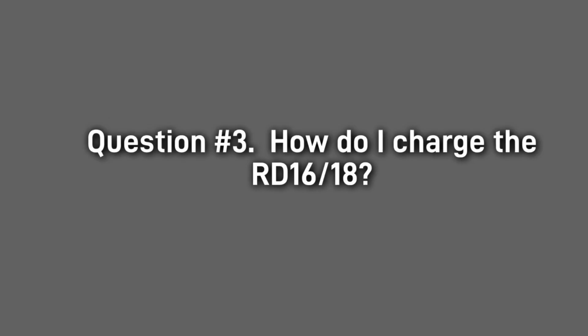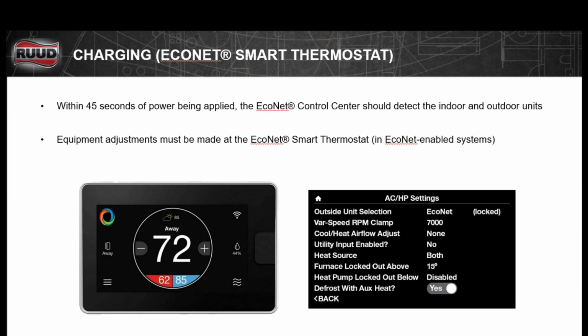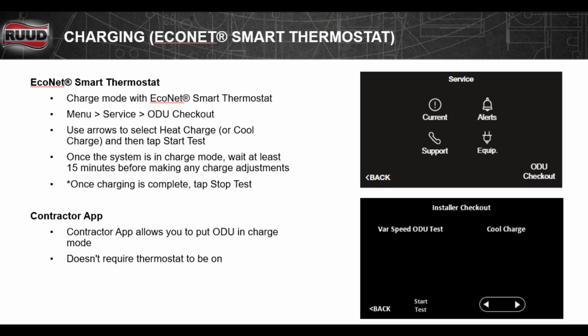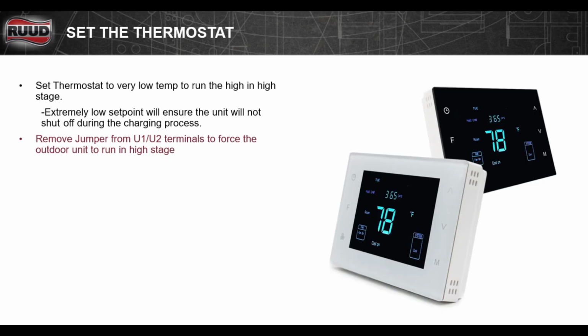Question number 3. How do I charge the RD16 and RD18 system? On the installs utilizing the EcoNet controller, we're going to navigate to the ODU checkout menu. We're going to put the system into cool charge and use the charging chart at the condenser in order to charge the system properly. If the system is legacy wired to a conventional 2-stage thermostat, we're going to set the thermostat to a very low set point.